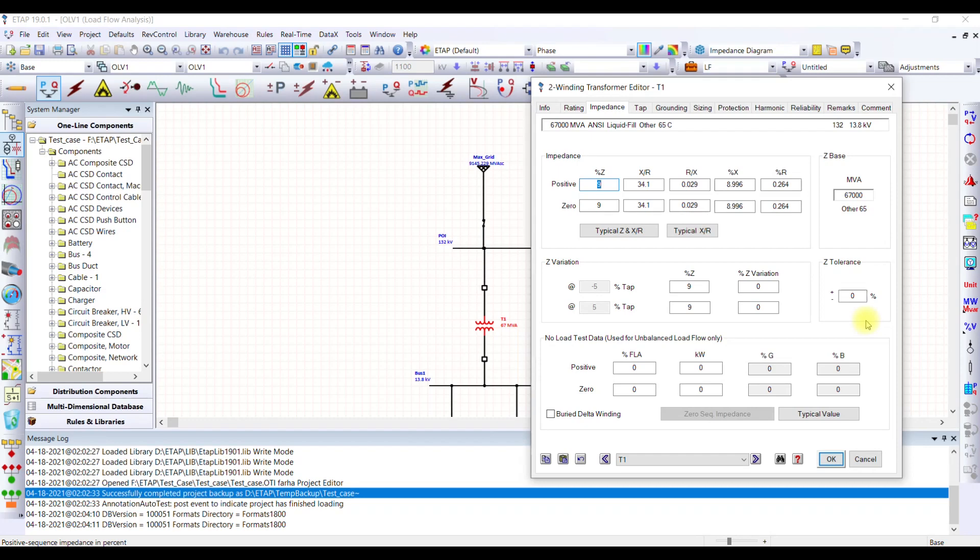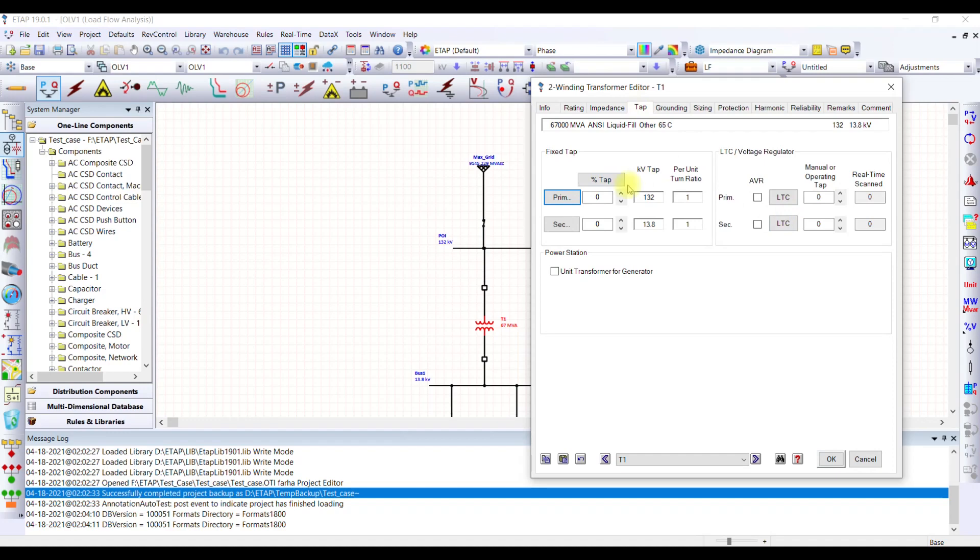For the short circuit level it will be reversed. The lower the impedance, the more will be the short circuit current. This way you select this tolerance and ETAP takes care of this. Similarly, the other tabs are there. If you want to change the tap positions, the tap positions can be changed from here.